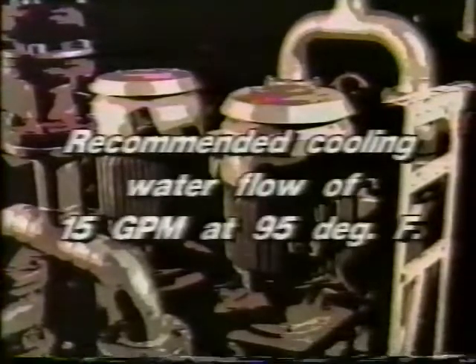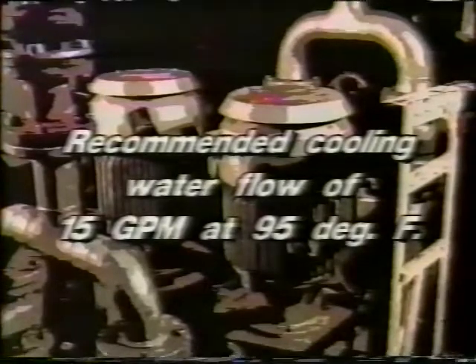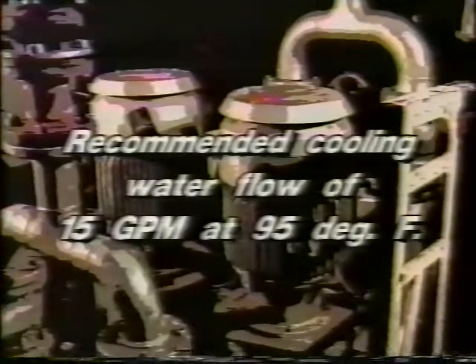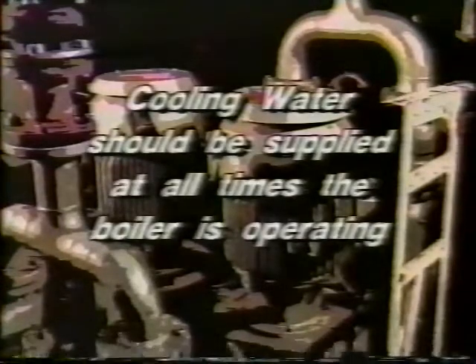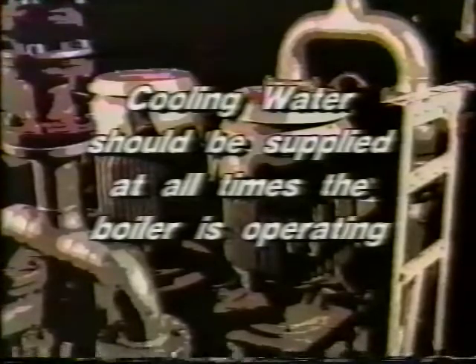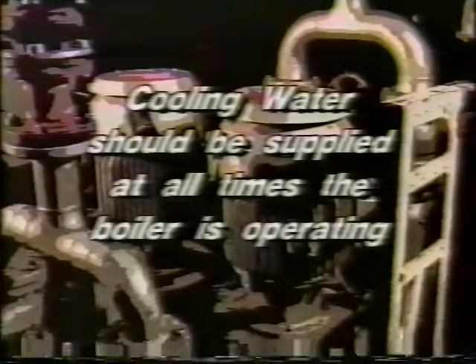The pump manufacturer recommends a cooling water flow of 15 GPM when the cooling water supply temperature is 95 degrees Fahrenheit. Cooling water to both recirc pumps should be supplied at all times that the boiler is operating, unless a pump is being serviced or replaced.